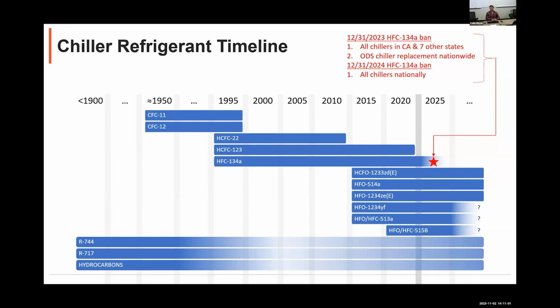It is getting some negative attention in Europe, and I believe there are some bans on this refrigerant in Europe because of another 3-letter acronym. So we've solved ODP, we've solved GWP. The next acronym is TFA, which is trifluoroacetic acid. And HFO 1234YF apparently breaks down into a high concentration of TFA. So that's sort of the newest concern.